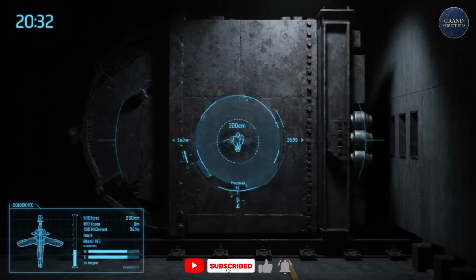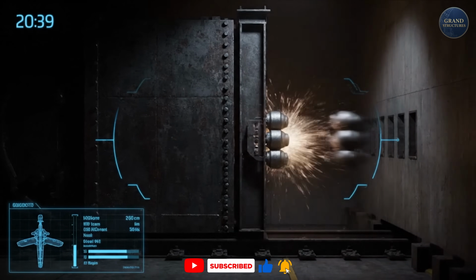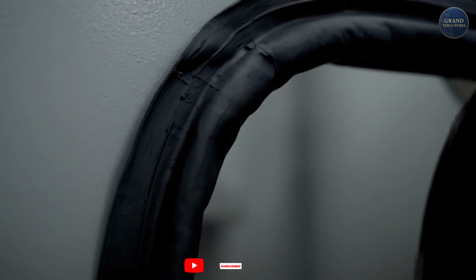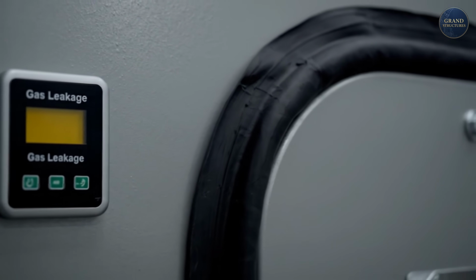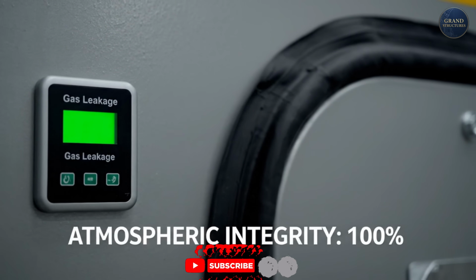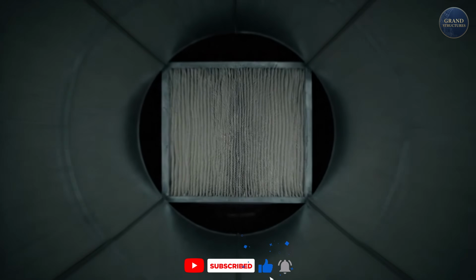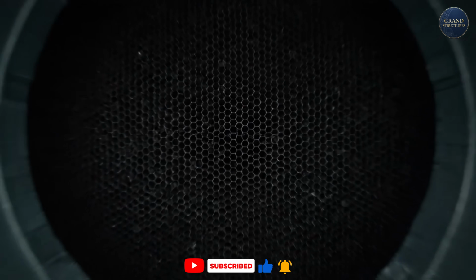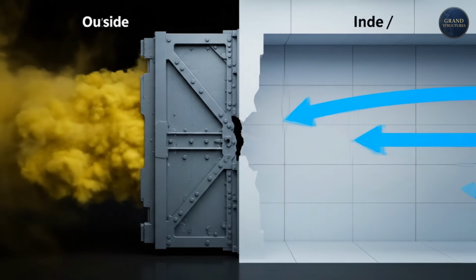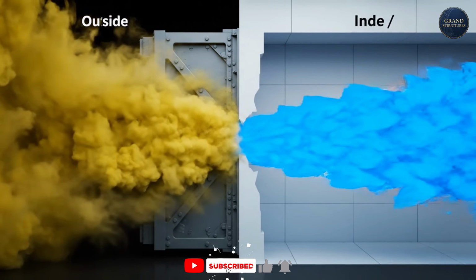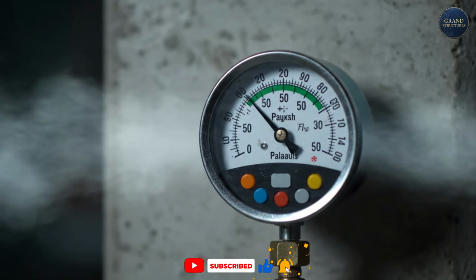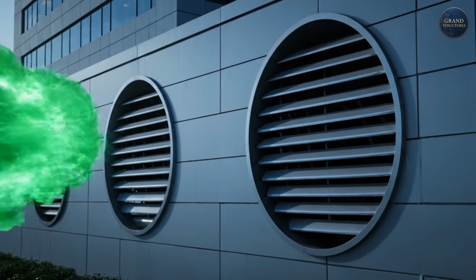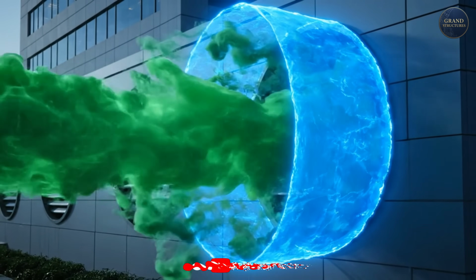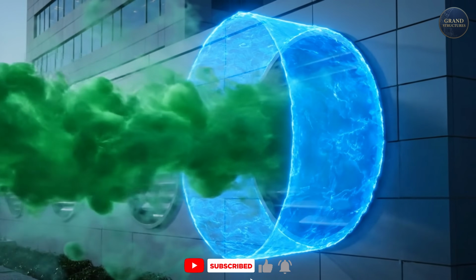The Rambam Underground Hospital was designed to survive that. When the threat level escalates, 20-ton steel blast doors seal every entrance. The facility becomes 100% airtight. Then the HVAC system switches into overpressure mode. Massive HEPA filters and activated carbon filters scrub incoming air, removing chemical agents, biological particles, and radioactive dust. But here's the genius: the system pumps air faster than it exhausts it, creating positive internal pressure. The air pressure inside the hospital is slightly higher than outside.